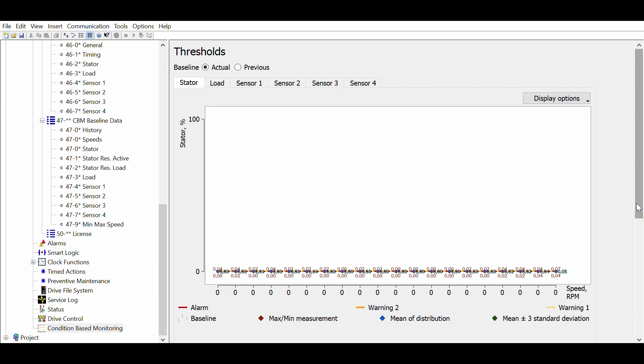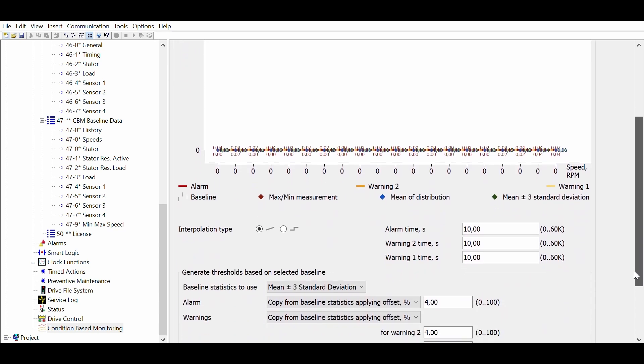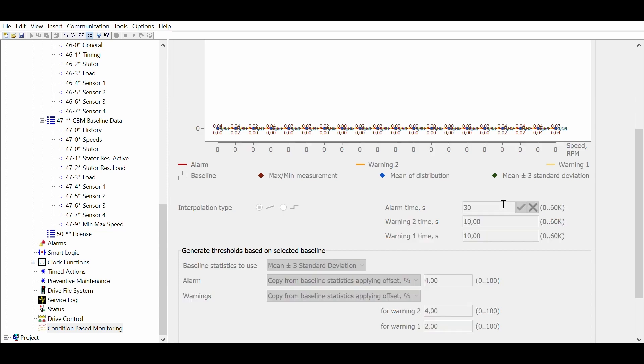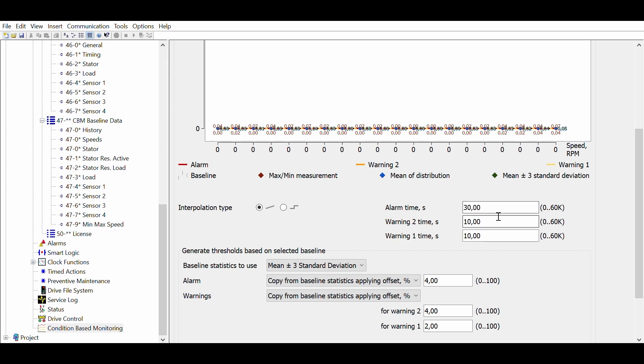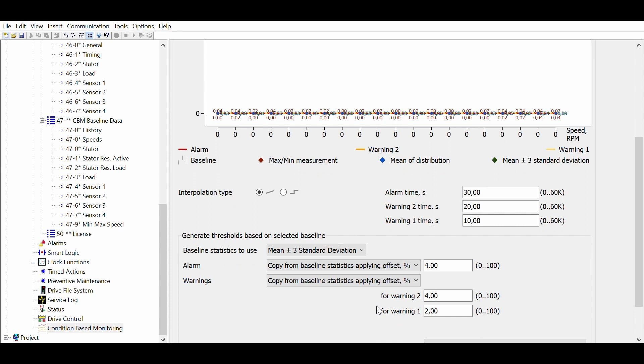Now, let's look at the threshold settings. We start with the stator monitoring function. For all functions it is possible to set the reaction time for the alarm and the two warning levels. This is useful to avoid nuisance warnings, for example during ramp up or other transitory conditions.